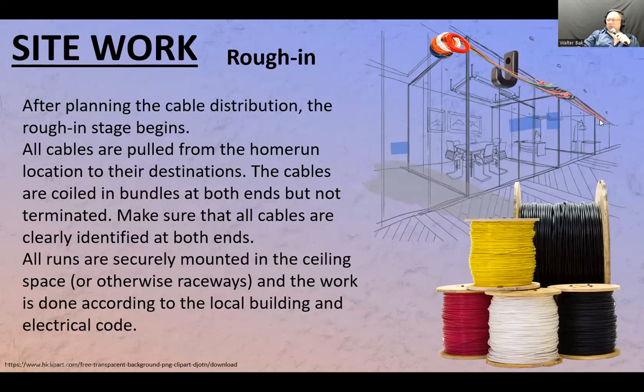Sometimes if you do things right, and if you mount the J hooks at the right angle with one turn, you might get away with pulling a bundle, but you're going to have to mount them a certain way and tie them a certain way to a string. Yes, it's possible to pull J hooks at the right angle. So let's say if you pull the wires from here and around the corner, and then pull them right here, that's going to be a pulling force. Yes, you can arrange those J hooks in the ceiling so that you can pull that. But when you're starting out, I would just do straight lines first.